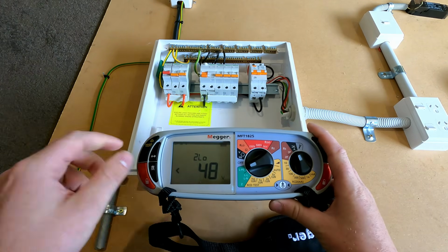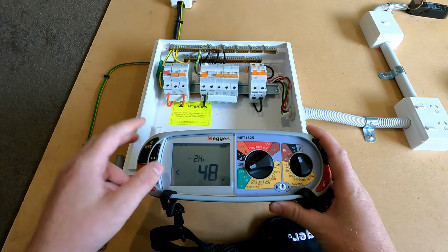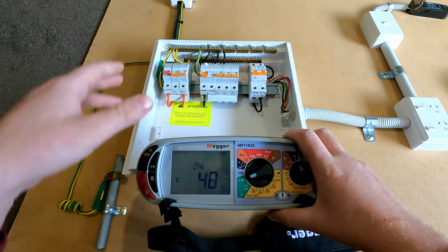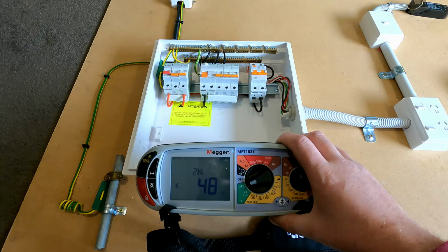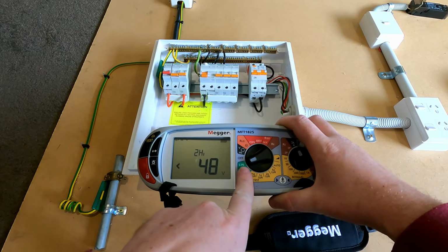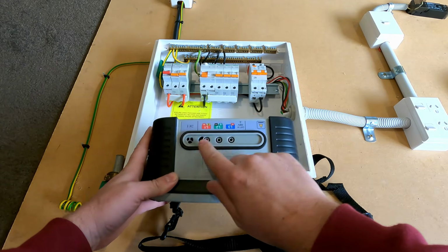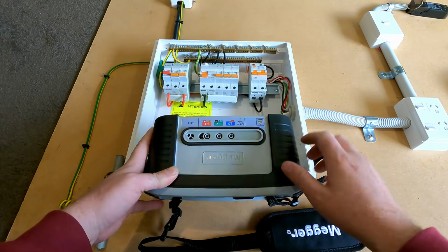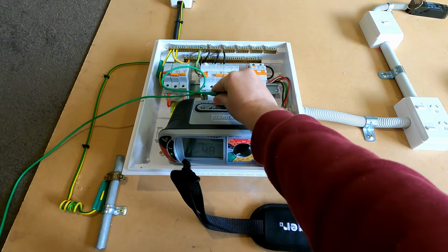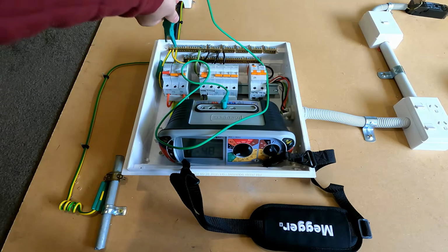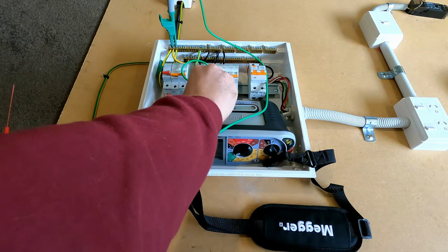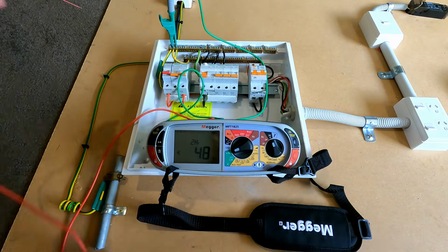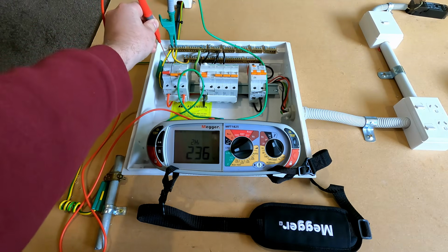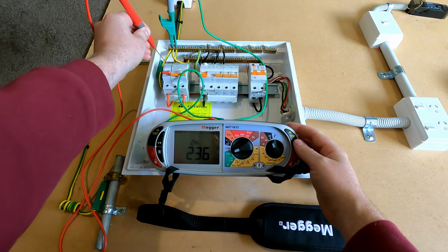So our first test we'll be doing will be our 2 lead high current test, and we're going to go on the line side of the main switch there. We've got it on line to earth, so what we're going to want is to put one into the line and one into the earth of this. Here goes our earth lead, and we'll hook this one onto the earth bar, throw our red lead in, and put it on the line side of the main switch. And then we just simply push test.